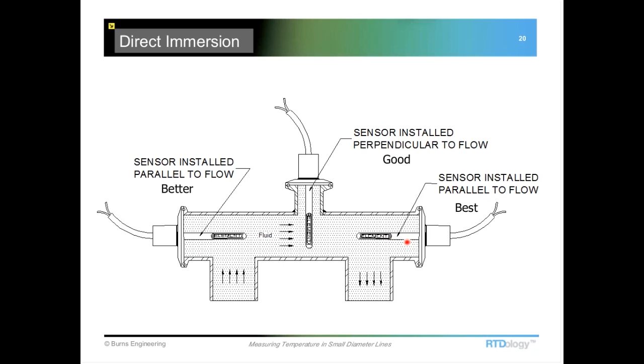The better location would be to have the fluid coming directly at the tip of the sensor. That way we get a lot of good washout back here in this stagnant portion of the T. And we can run this sensor down the run of the pipe with sufficient immersion so that we would get a good accurate measurement, and we minimize the effects of stem conduction.